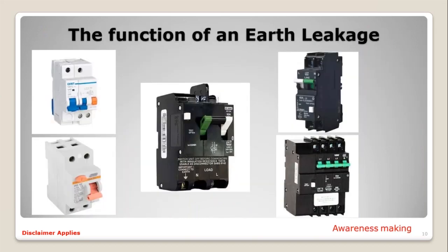So we are aware that in older houses, when you do a geyser replacement, most of the installations at that time did not connect the geyser through the earth leakage. So if you can identify something like that, make the homeowner aware, to make sure that an electrician can come out and see that the geyser circuit is connected through the earth leakage. And details of these will be discussed at a later stage. But let me go quickly through the function and the importance of the earthing for this earth leakage.